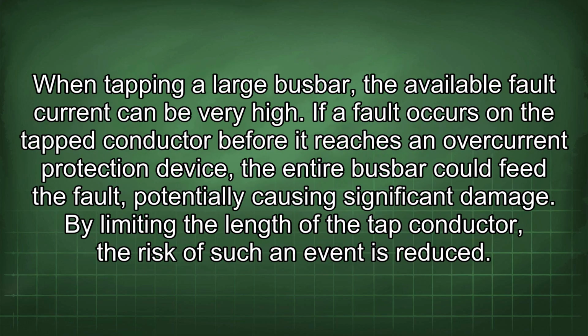When tapping a large busbar, the available fault current can be very high. If a fault occurs on the tapped conductor before it reaches an overcurrent protection device, the entire busbar could feed the fault, potentially causing significant damage. By limiting the length of the tap conductor, the risk of such an event is reduced.